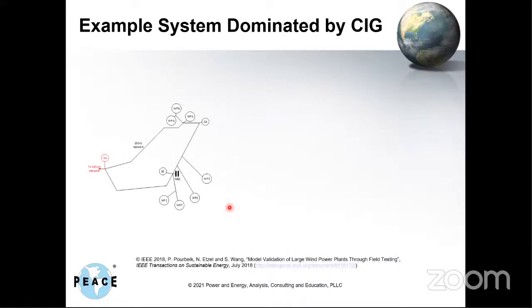Just real quick, some examples. This is a real system dominated by a whole bunch of wind plants. We went through and one by one did step tests on the plants, then appropriately parameterized the standard models to fit the plant. The parameters were actually derived by looking into the software of the actual plant controls, taking the gains from there and properly per-unitizing them to put into the model. So we're not doing some fancy optimization, we're basing it on the actual control strategy.